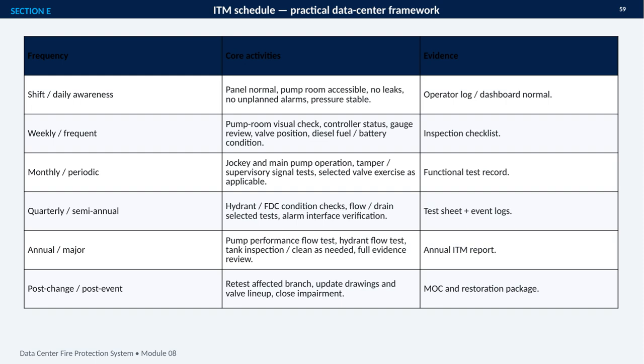stable. Weekly checks go deeper, covering the pump room, controller, gauges, valve positions, and diesel fuel or battery condition. Monthly activities include operating the jockey and main pumps, testing supervisory signals, and exercising selected valves where applicable. Quarterly or semi-annual work adds hydrant and fire department connection checks, selected flow or drain tests, and alarm interface verification.